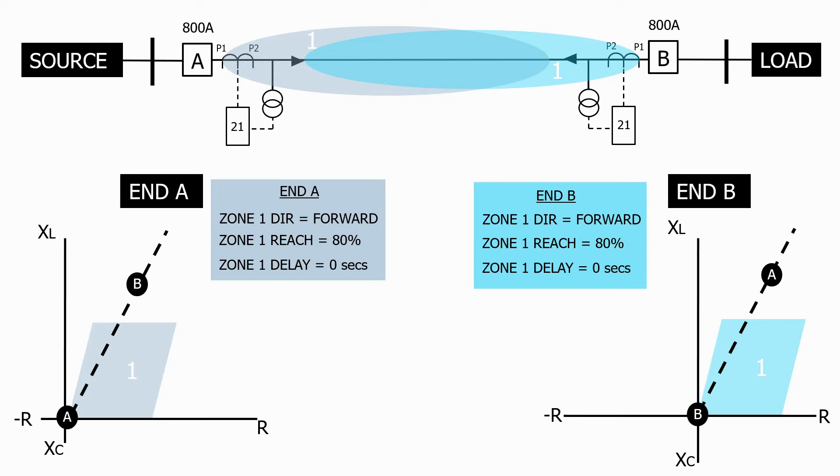Let's now energize the feeder. As we can see at end A the load characteristic is well outside the zone 1 protection coverage. At end B the load current is flowing in the reverse direction, so the load characteristic appears in quadrant 3 of the impedance graph.